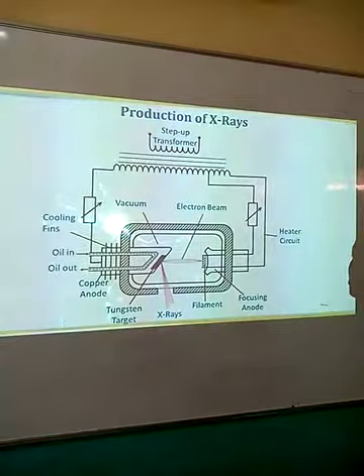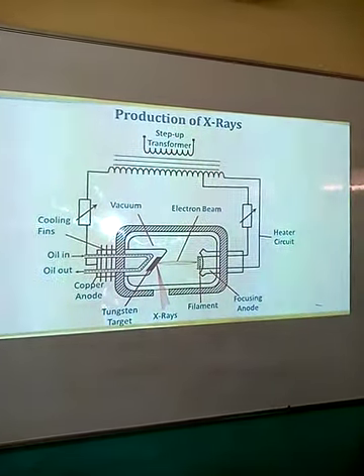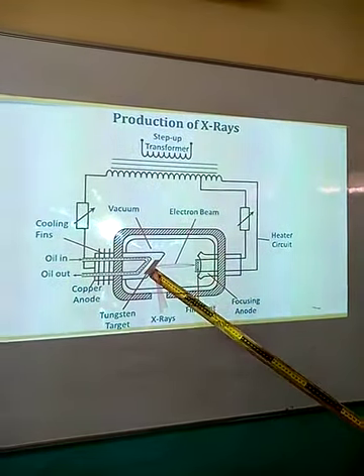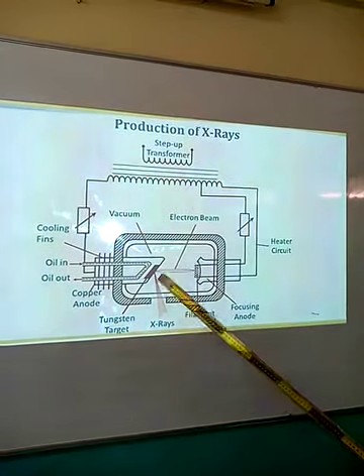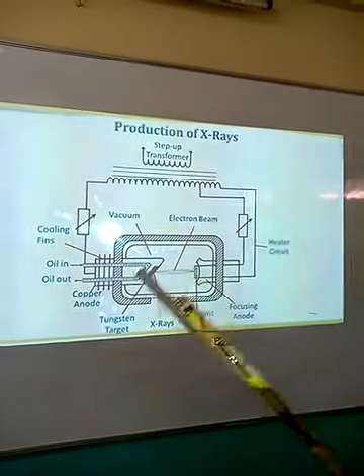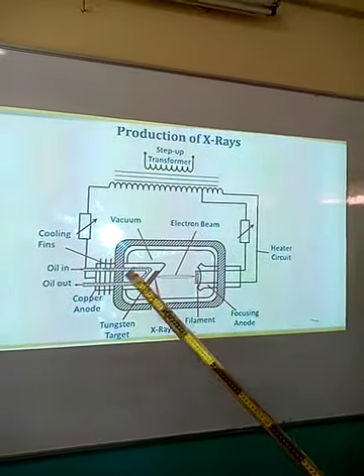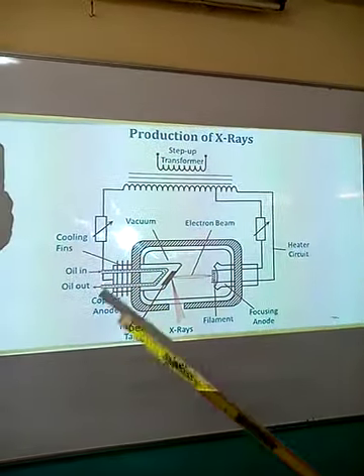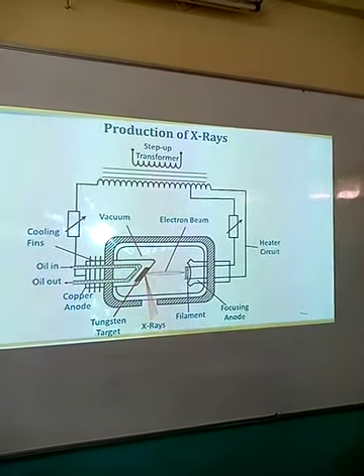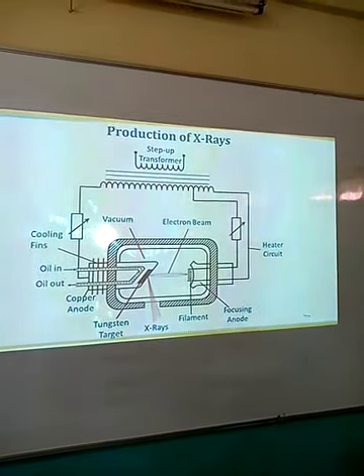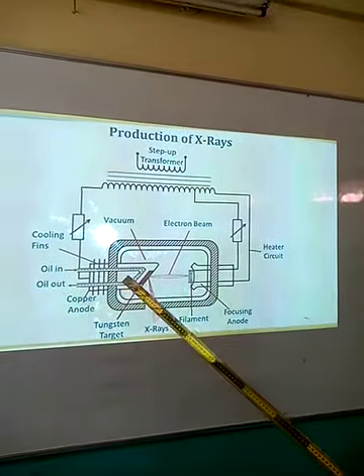The target is made up of tungsten. Tungsten is a material of very high boiling point. This enables the anode to absorb the large amount of heat being produced at the point of impact. The cooling of the anode is done by the circulation of oil in and out of the anode, and also by the presence of cooling fins, which are normally made up of copper. This is meant to dissipate or conduct the already produced heat away from the anode.